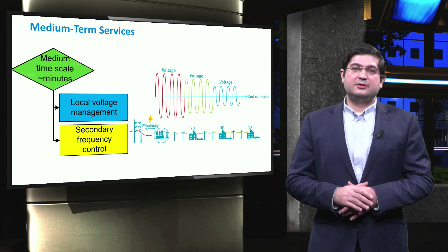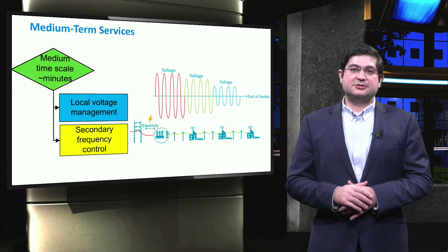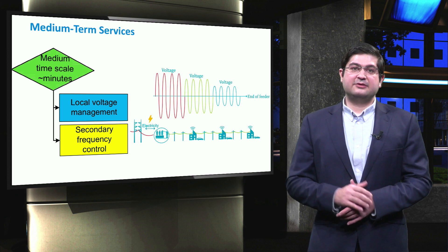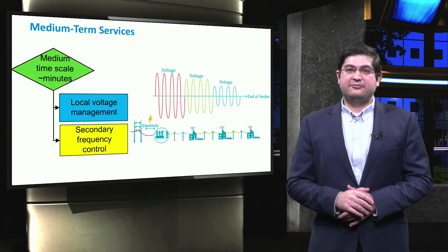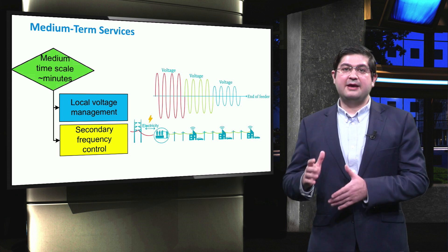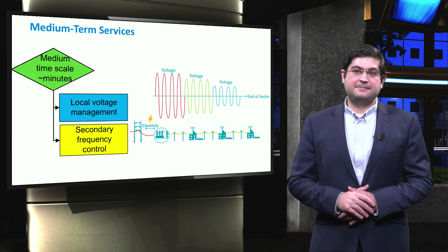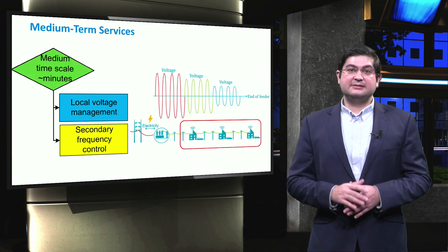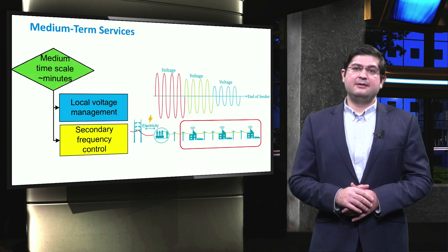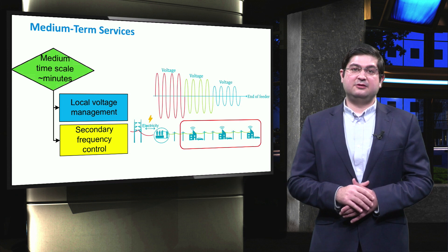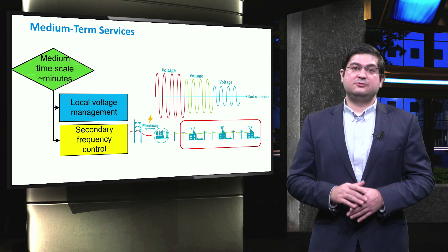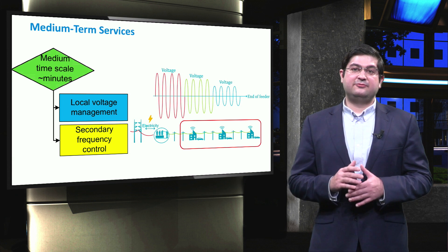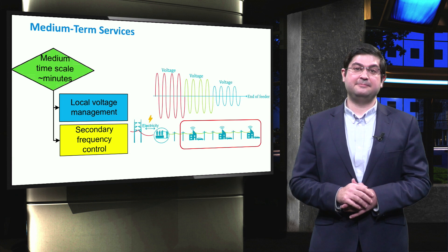The voltage across a low-voltage distribution grid can be managed in such a way that no over-voltage or under-voltage problem occurs. As shown in the figure, typically the voltage across a feeder decreases from the head of the feeder to the end of the feeder due to the voltage drop across the lines. The voltage can be controlled either by the tap changers of the transformers, or by demand side and supply side management across the feeder. Another medium-term example is secondary frequency control, also known as load frequency control or automatic generation control of interconnected power systems. This service is the main responsible for restoring the frequency in the whole system after a disturbance.